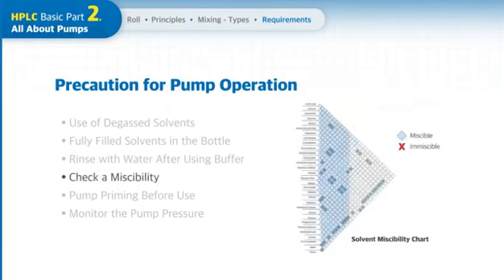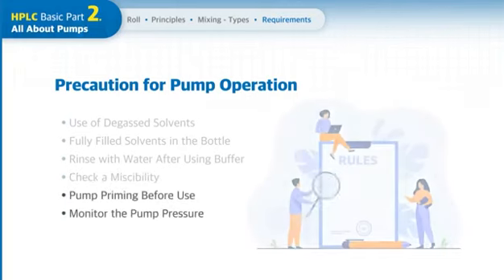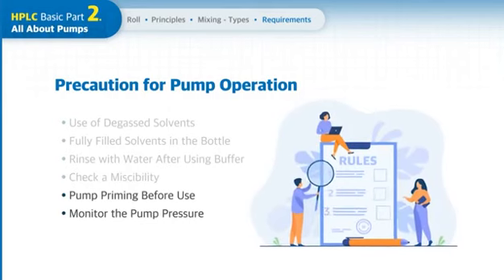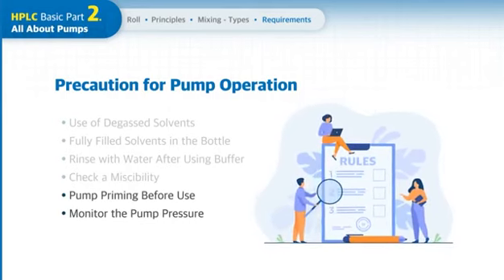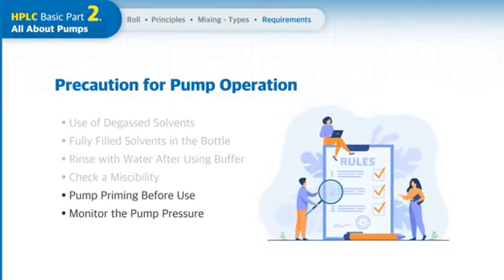In the use of more than 2 mobile phases, you should check whether those solvents are fully miscible enough for a stable flow rate. Other than these, pump priming should be performed before use, and you have to monitor the pump pressure carefully during analysis.